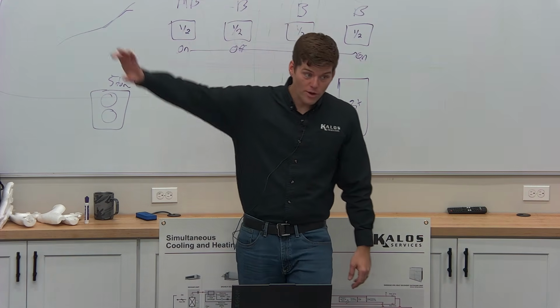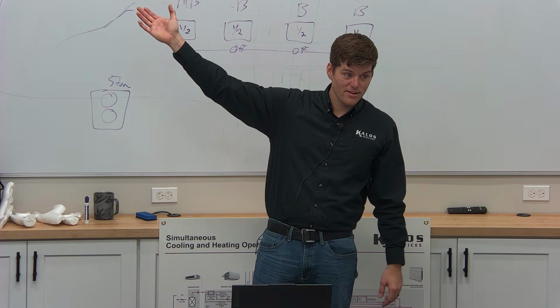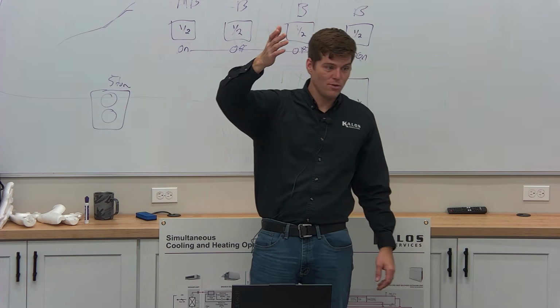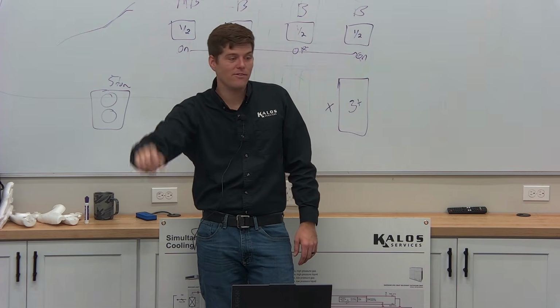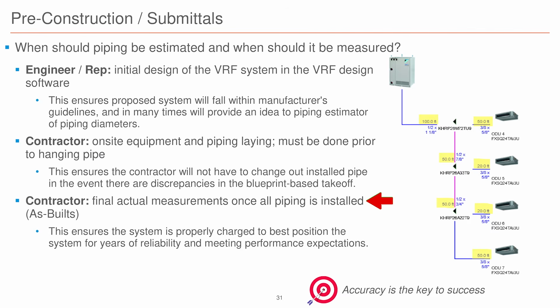That change should then go into the report and be rerun. You're not doing 3/8, 5/8 anymore. You're doing 7/8 and 1/2 inch. And then last and final, you have as-built, which is where that one person who did the installation has all the numbers that they need. They put it into one specific drawing. We make a final copy and we say, okay, you didn't do the installation, but you're doing the startup. Here is your final copy of the installation that says that system needs 23.8 pounds of refrigerant to start and run, according to the distances, according to the line sizes, all that stuff like that.